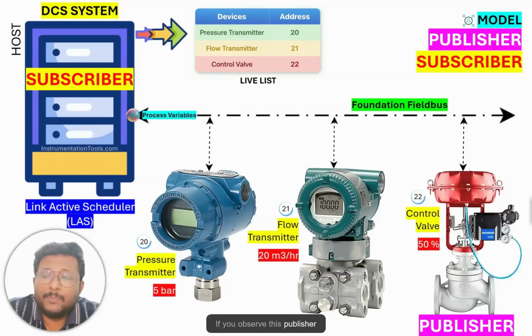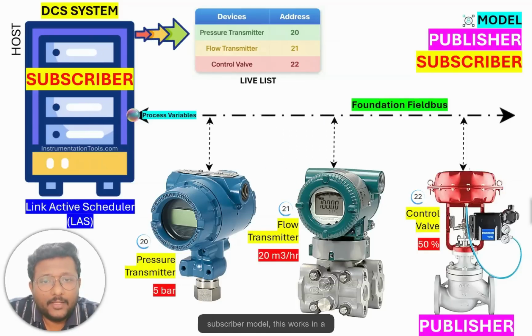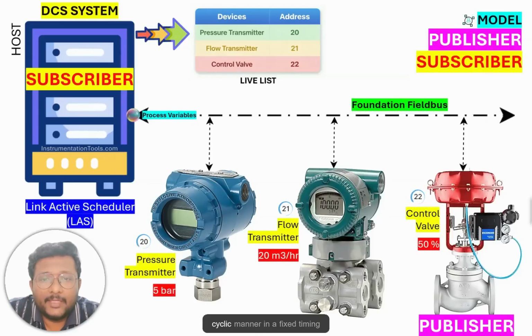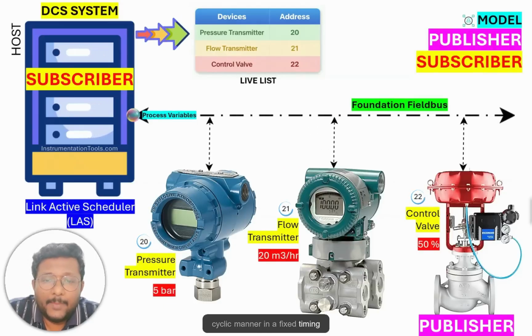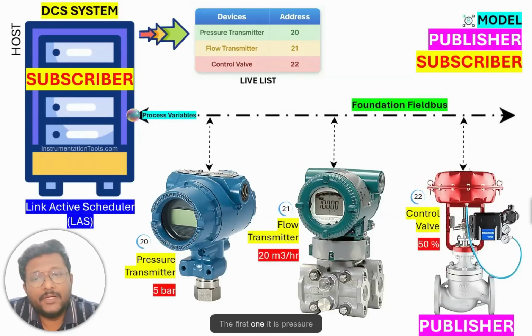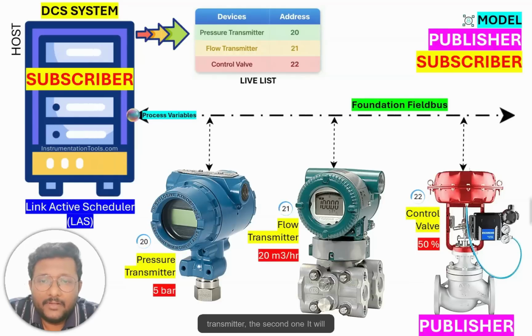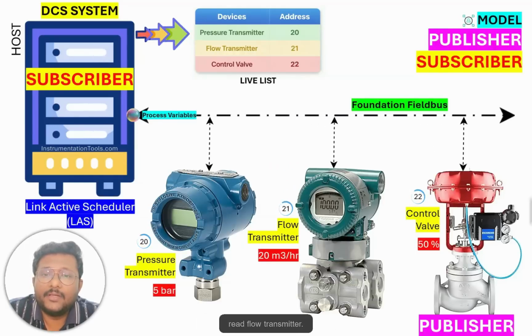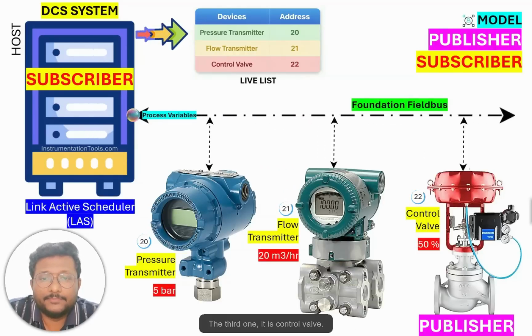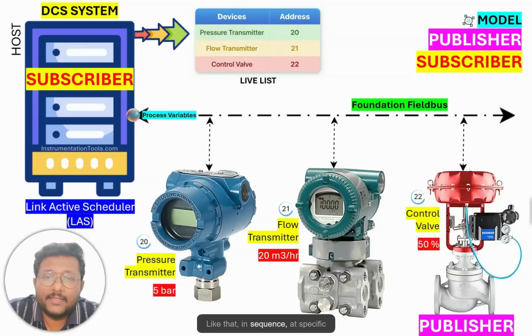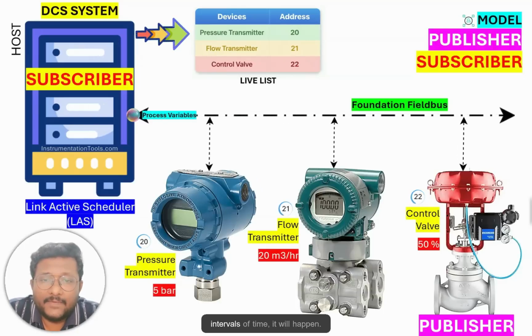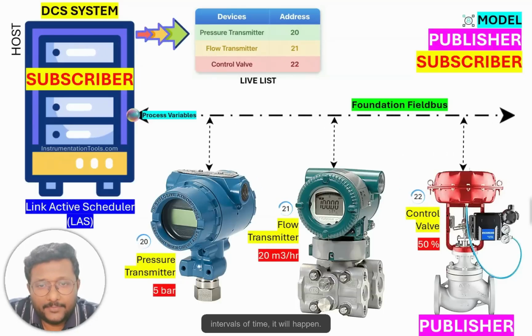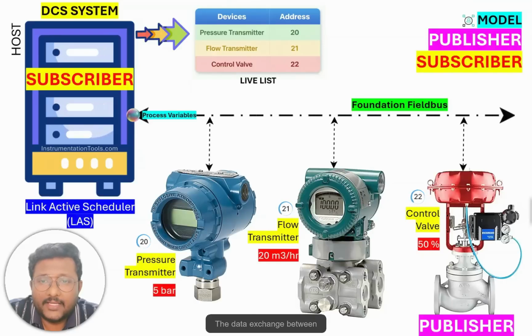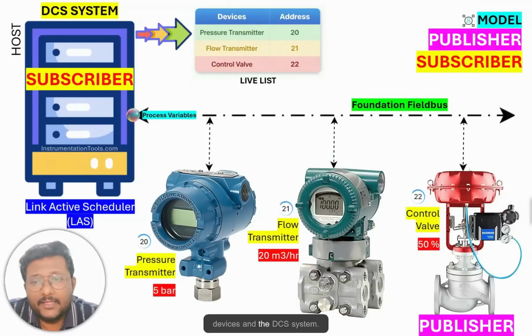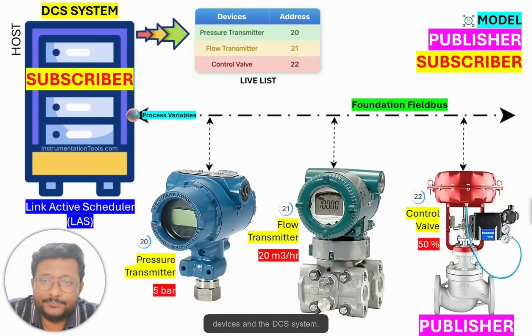If you observe this publisher subscriber model, it works in a cyclic manner in a fixed timing interval. The first one is the pressure transmitter, the second one it will read is the flow transmitter, the third one is the control valve. Like that, in sequence at specific intervals of time, data exchange between field devices and the DCS system happens.